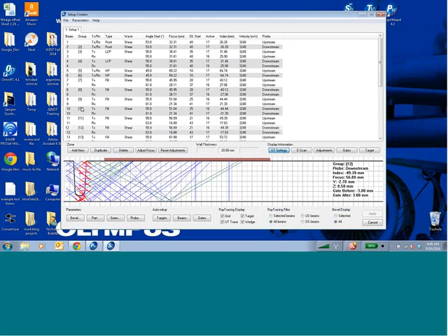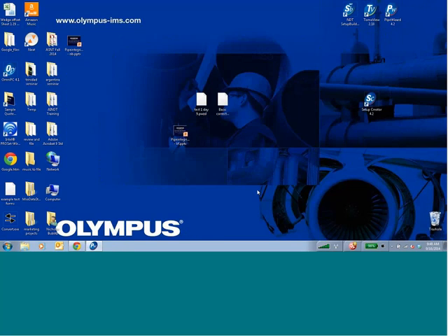After doing the joint, I basically just hit adjust, and it's going to throw all the beams in there and give me a theoretical positioning. I'm able to go back to the cal block and make micro adjustments by going over each reflector if I want to get a very good starting setup. So once that's done, I can go back and do some micro adjustment.